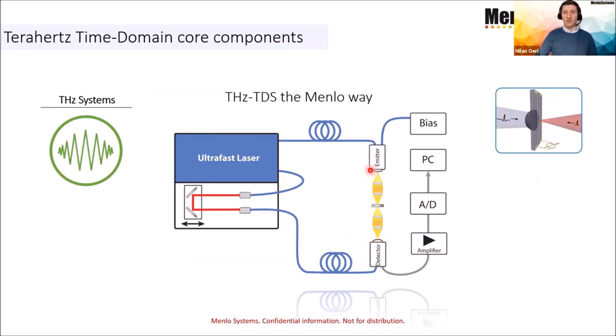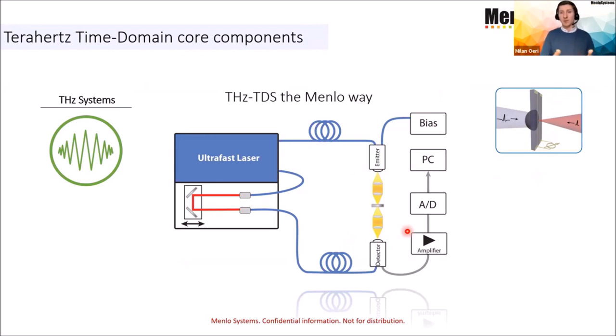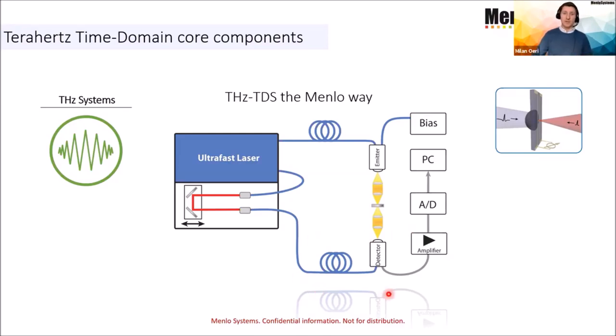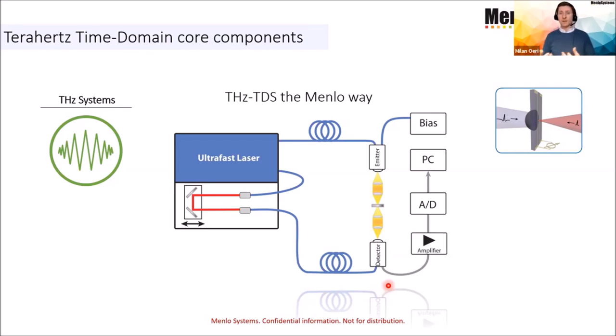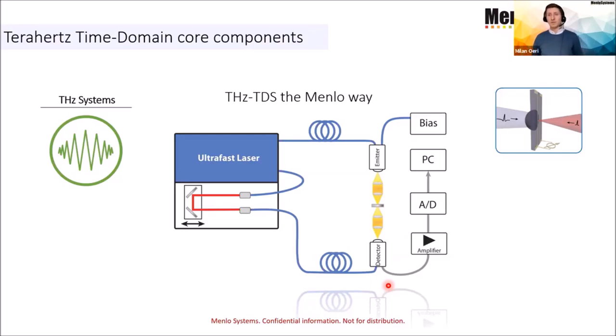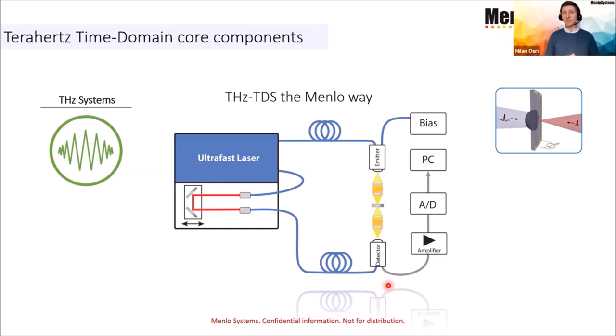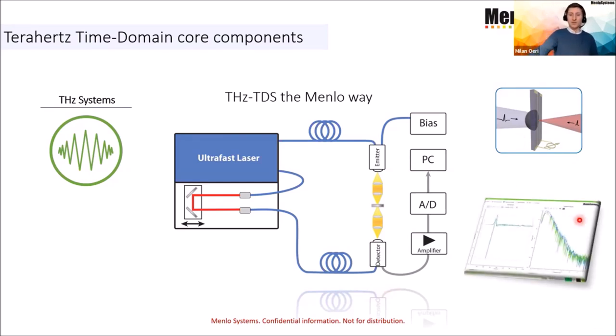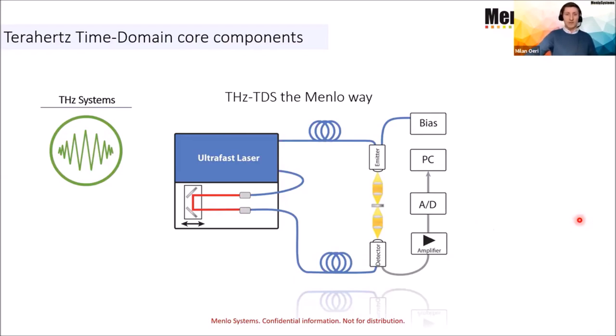You can apply different Terahertz optics, not only parabolic mirrors. Polymer lenses are also interesting because they are much easier to align in contrast to parabolic mirrors. It's the same principle on the detection side. An incoming optical pulse from this fiber, which is delayed in regard to the emitter arm, creates electron and hole pairs. In this case, no bias voltage must be applied because simply the incoming Terahertz wave acts as the accelerator of the electrons and hole pairs. The then measured photocurrent will be detected by an AD converter and computed by the PC to get the spectroscopic information or also the time domain data.